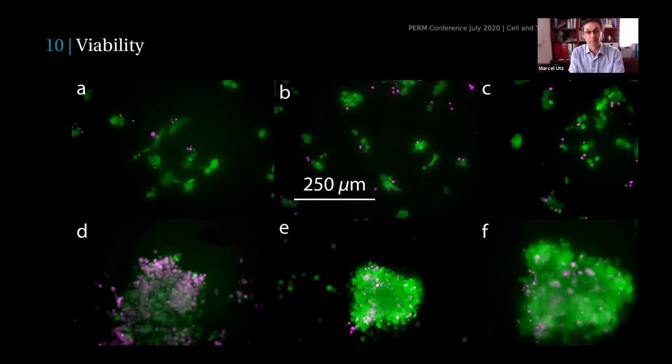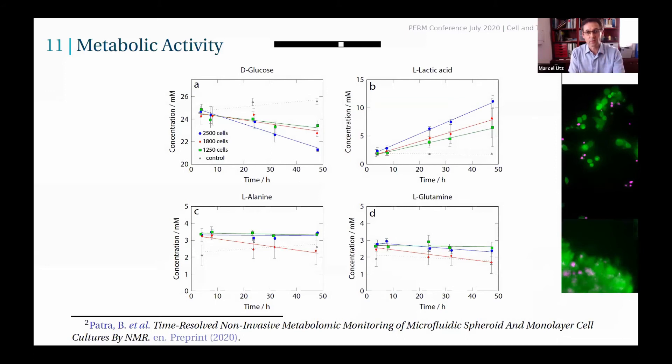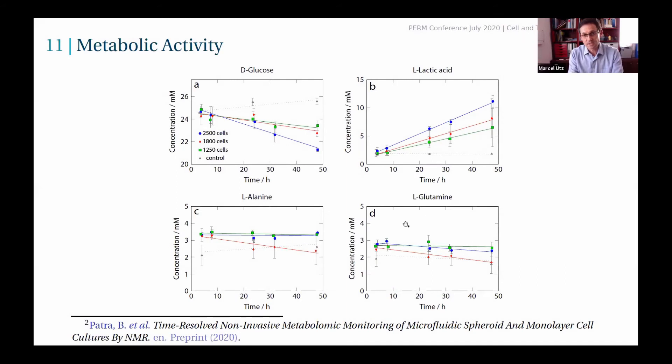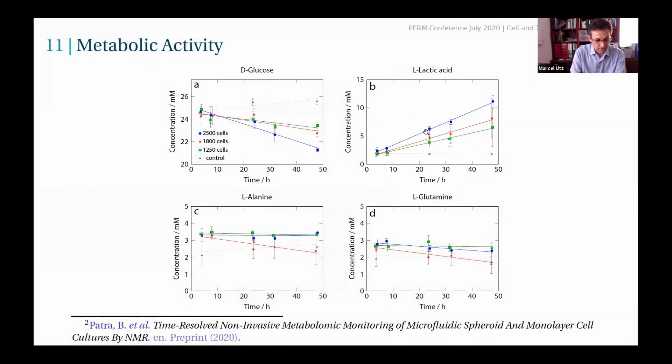We can get quantitative information on various metabolites, for example glucose and lactic acid, but also others like alanine, glutamine, and so on. You can see from the error bars here that we can work with kind of millimolar concentrations. I forgot to mention the sample chamber in these chips is about two and a half microliters, so about a hundred times smaller than a conventional NMR sample tube.